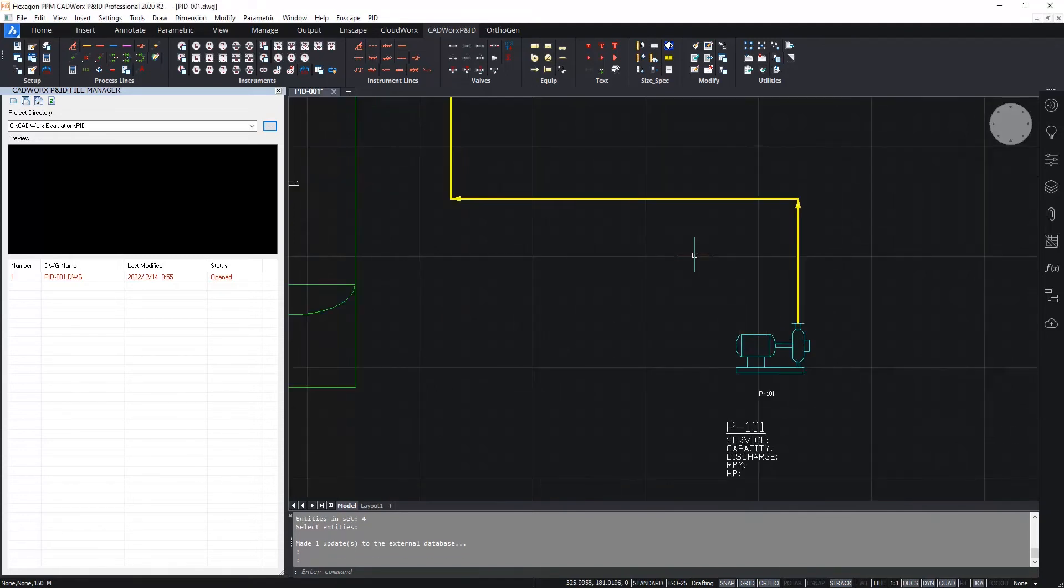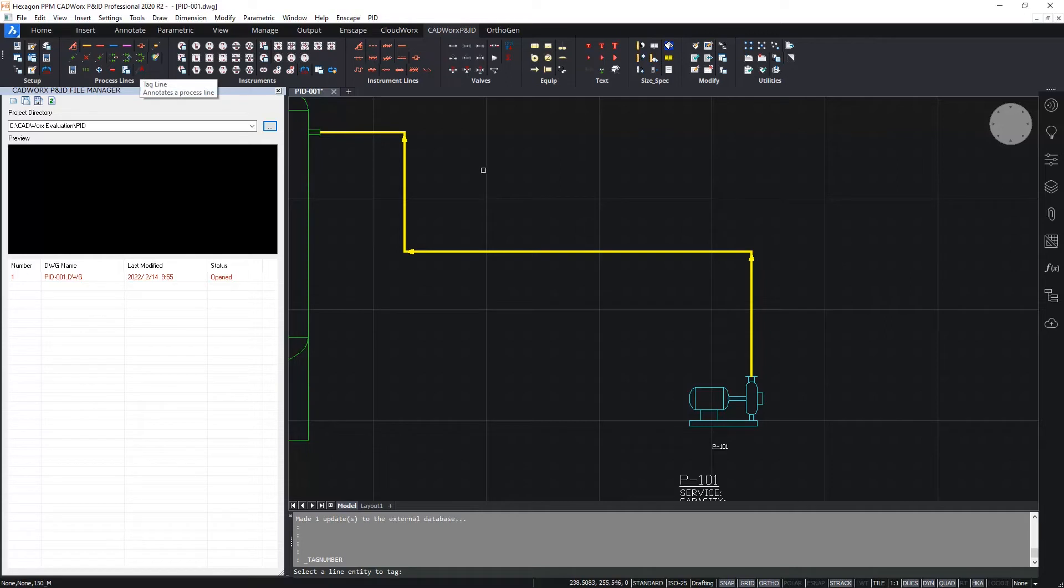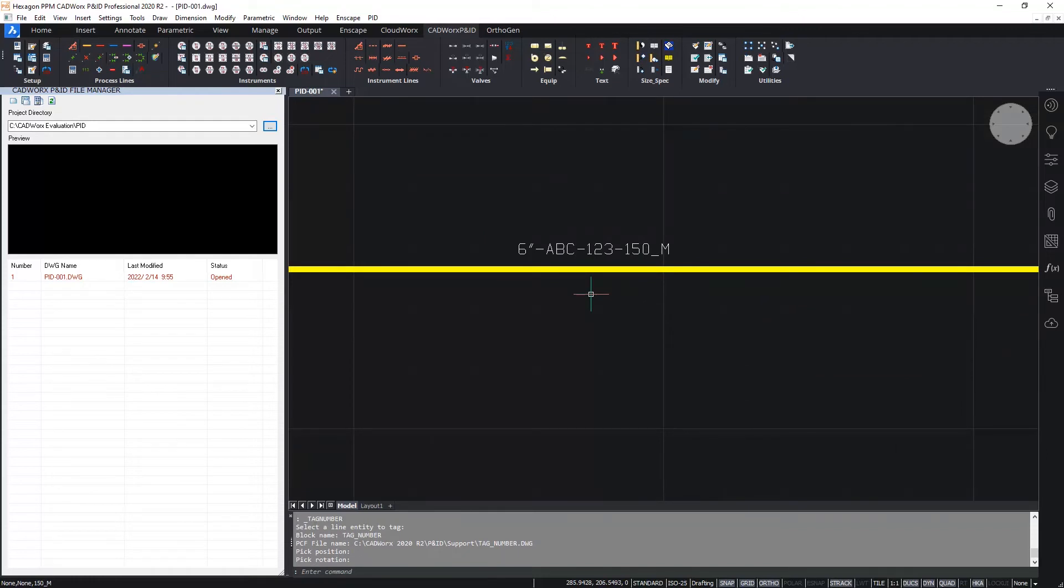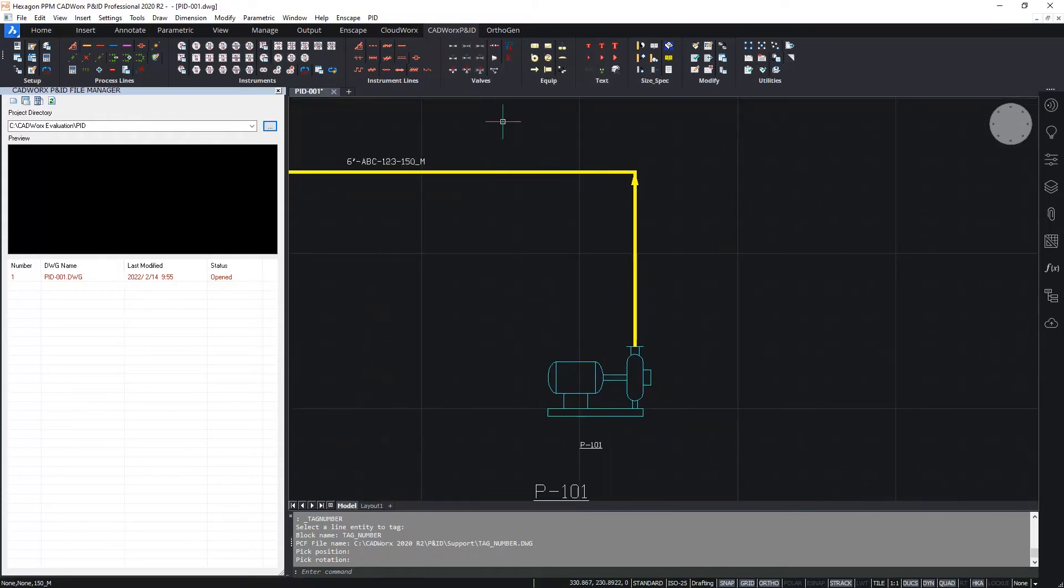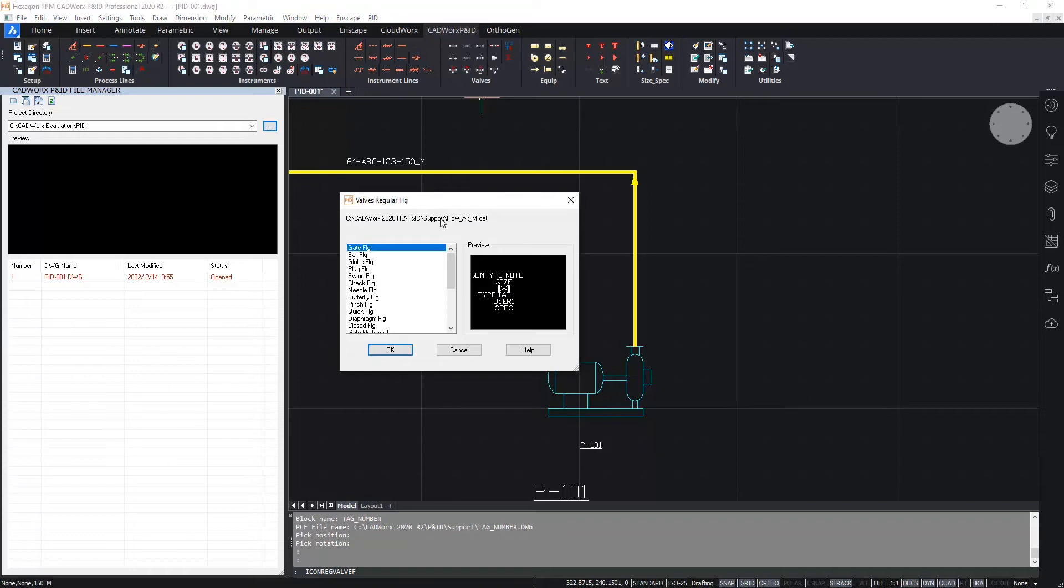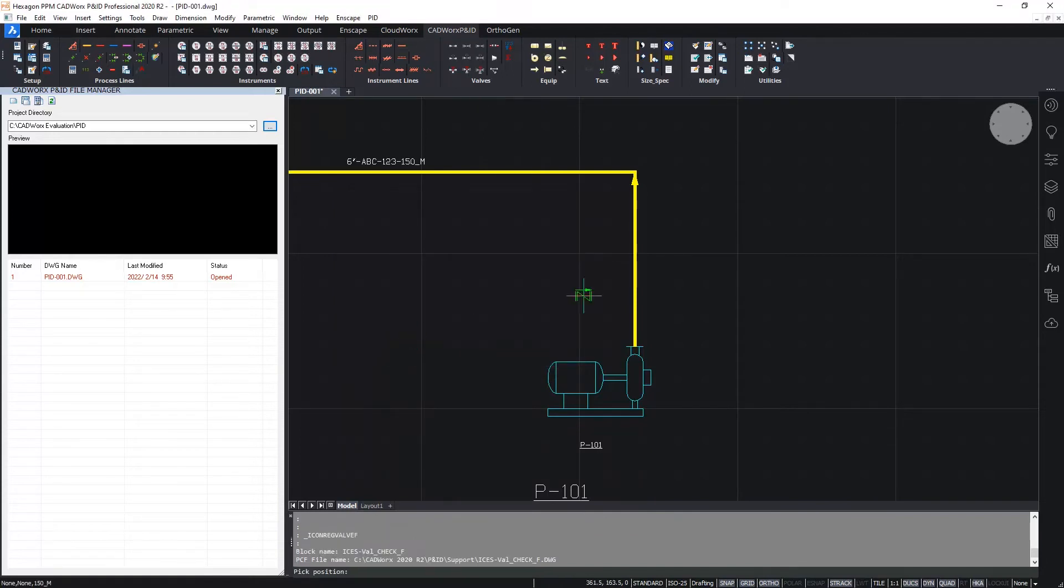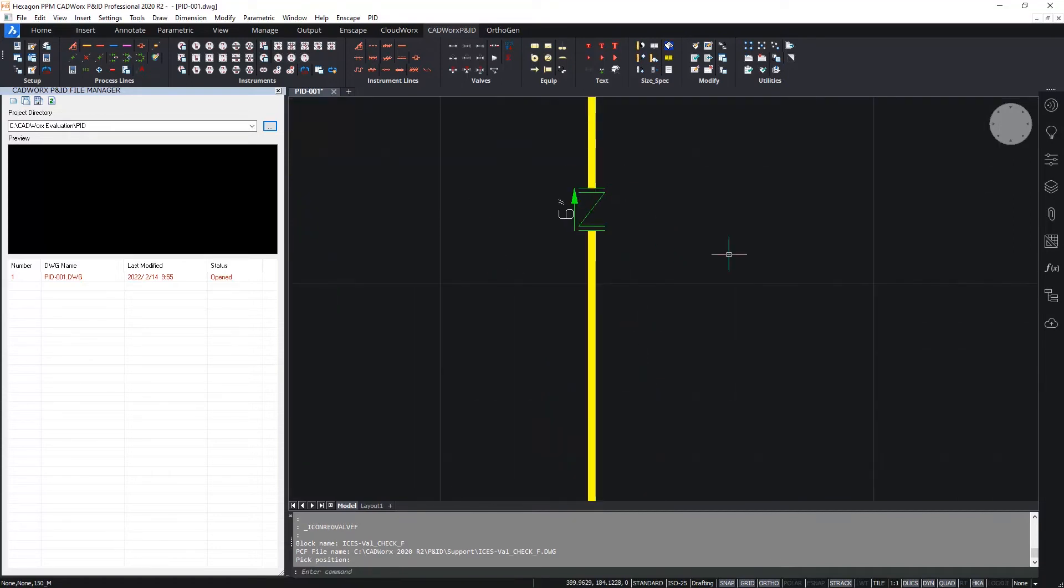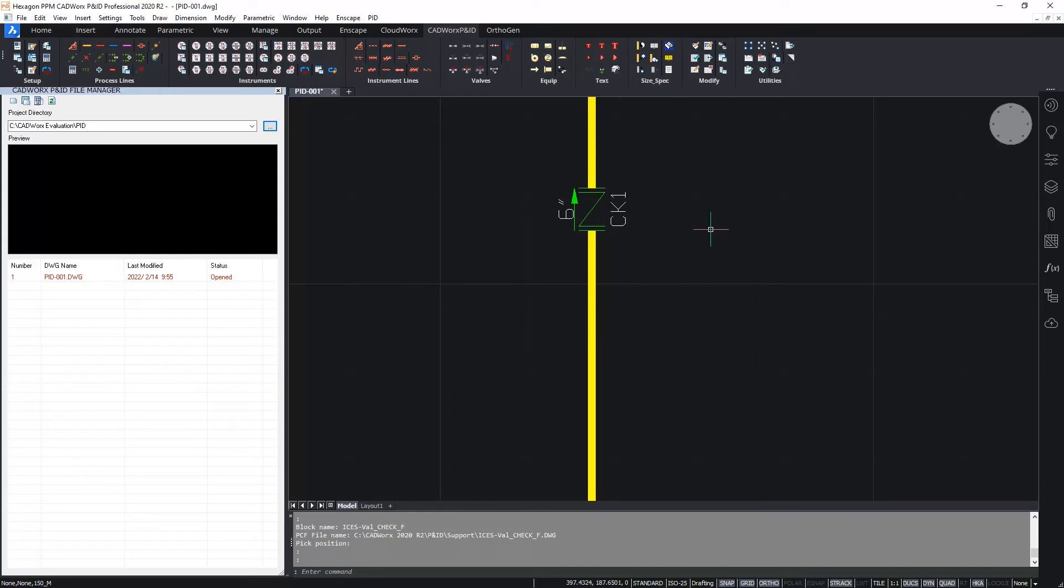And the final thing I'm going to do here is label that annotated onto the drawing by using this function here to tag the line. Pick the line and select the orientation of the tag. Like so, the tag data is picked up from the selected process line. Let's add some inline items now. I'm going to add a flanged valve here. I'm going to pick from the flanged valve icons. And on the pump discharge line, as is typical, let's insert a check valve, a flanged check valve from the symbols library. Insert that. Again, attach it onto the line. As you can see, the line is automatically trimmed back to fit the flanged valve in. And I will finish this off by just giving this a tag: CK1.